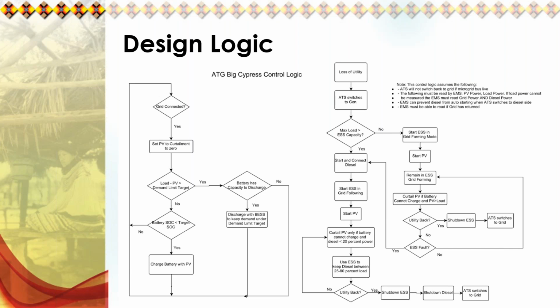So right now ATG is having to revise their logic diagram to facilitate what we are asking them to do in order to achieve the resilience we are looking for. Because if we had to keep the generators running incessantly in the event of another Hurricane Irma event, that really would not be practical. Being able to interrupt the run times for the generators and supplement it using the BESS would save on greenhouse gas emissions and on wear and tear on the generators. And if any maintenance needs to occur on the generators, it can take place while it's down, and the facility will still be able to run.